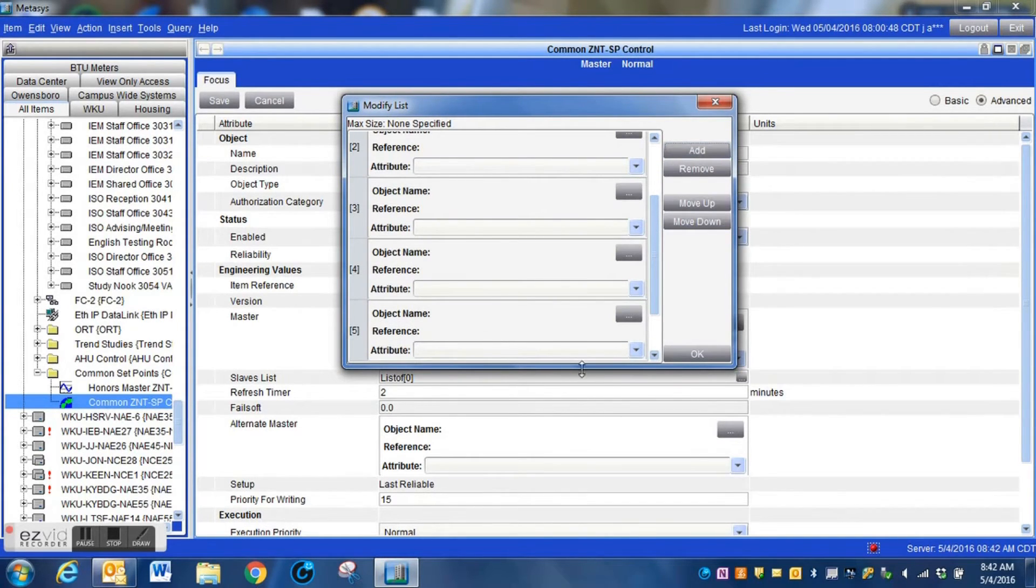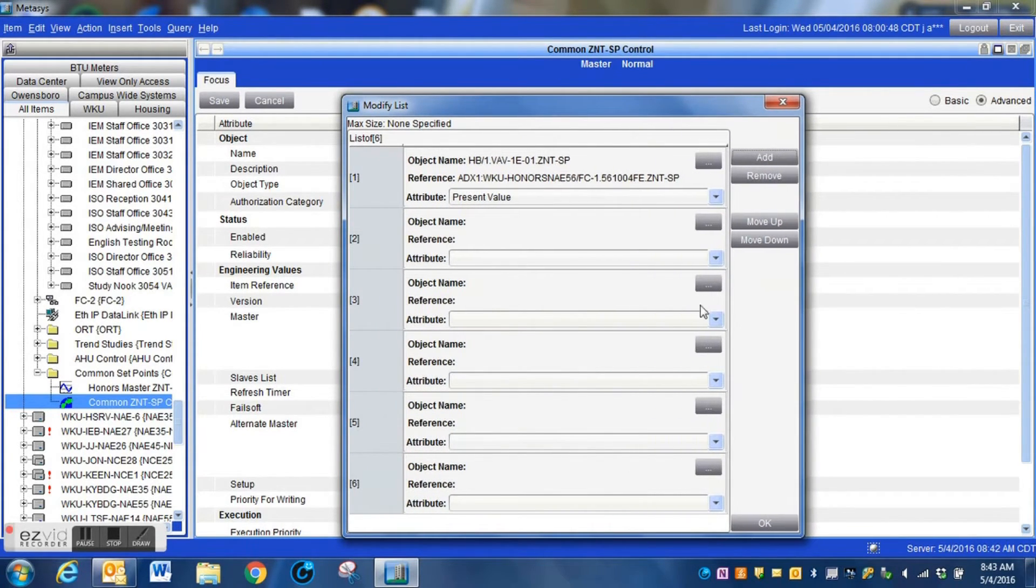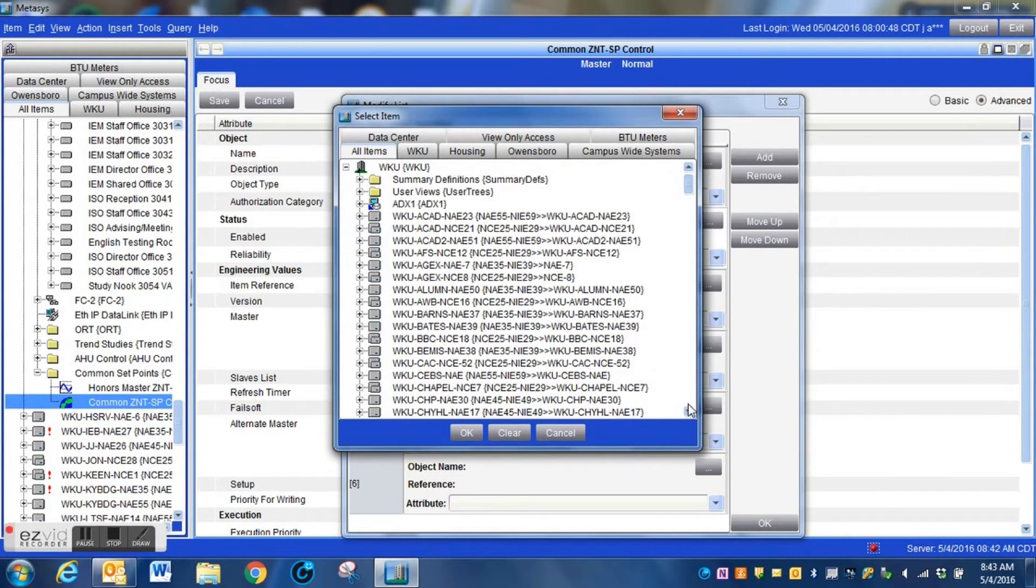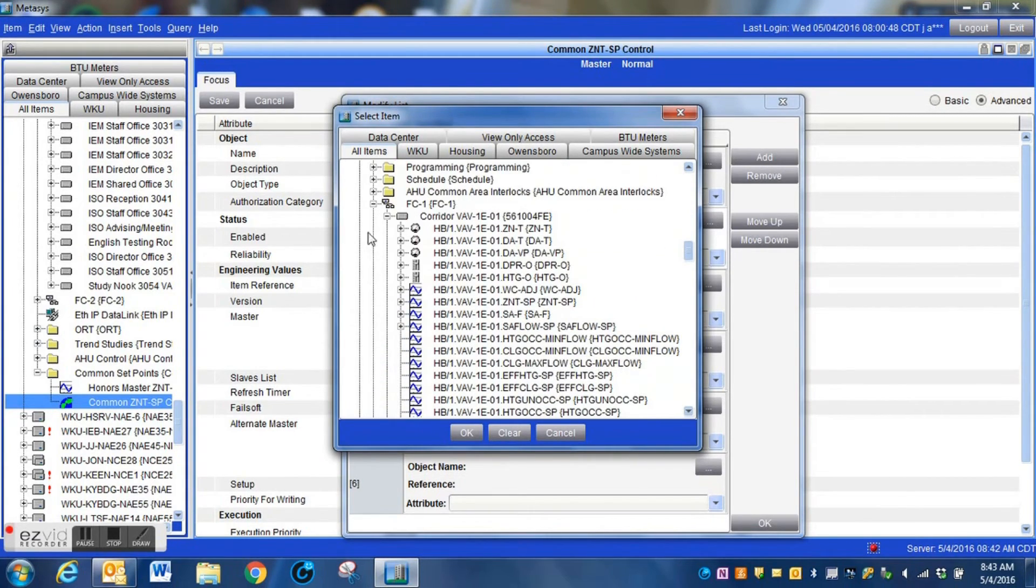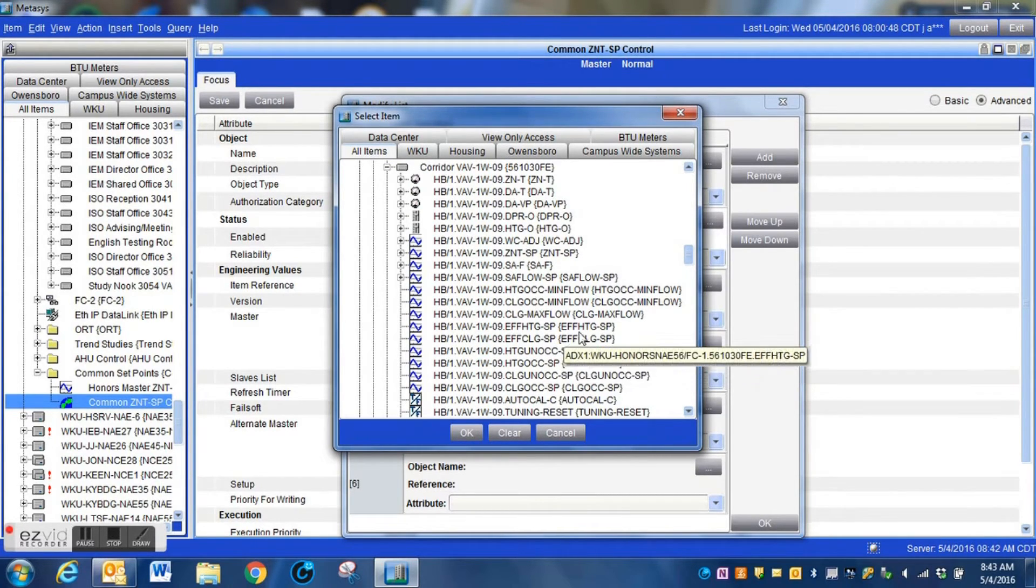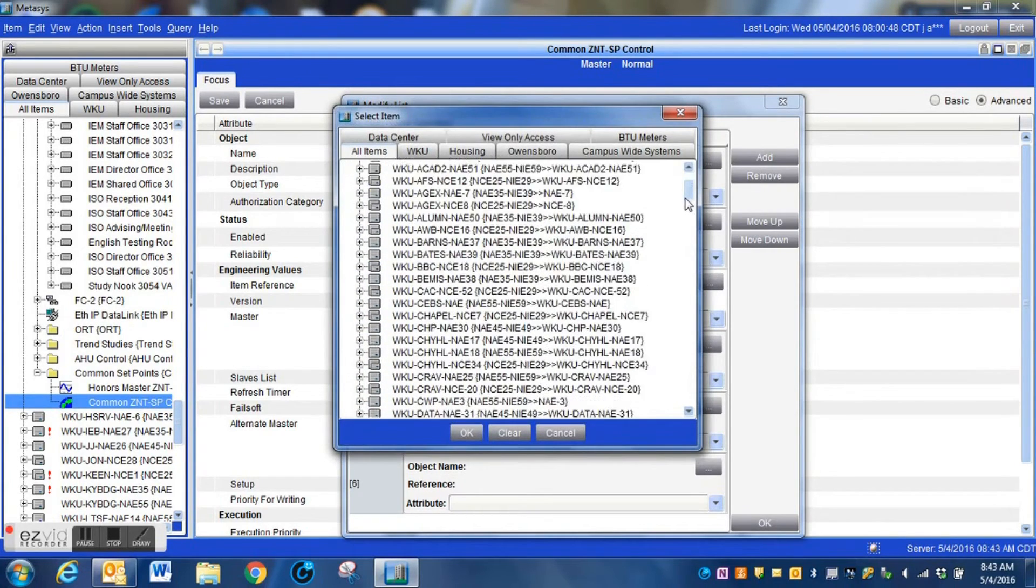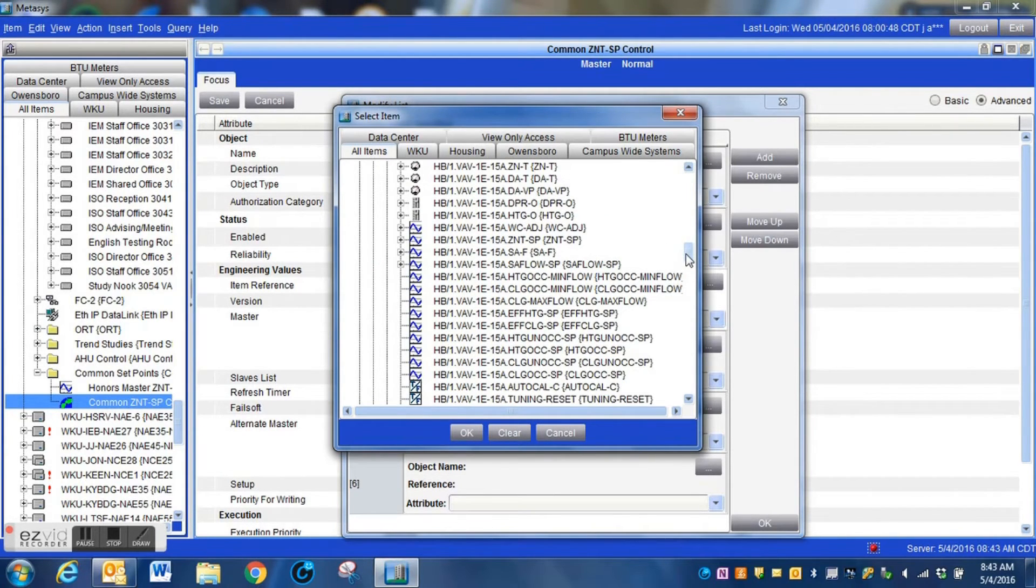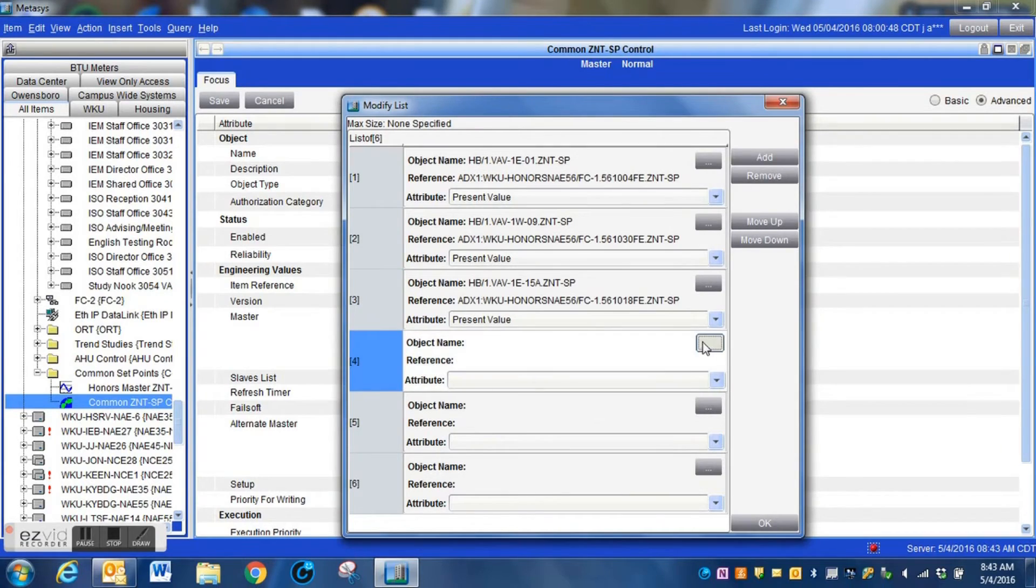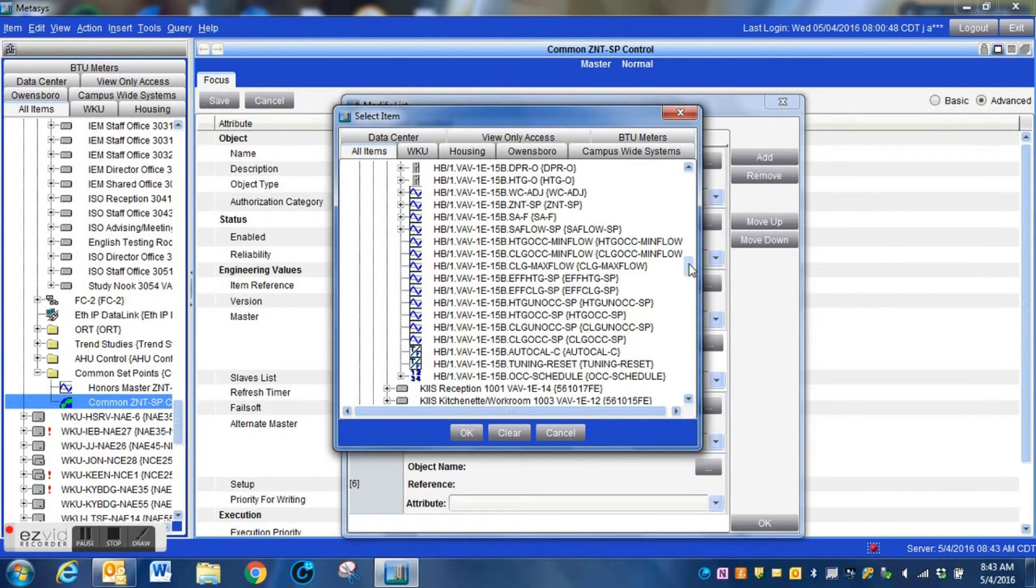We're going to add a few more of these. You can add several, five or six. Add those to your system, go back and find those values within your system, and then save your work regularly. You'll see that it will slow down. The more of these you add to your list, the slower your system is going to perform until you get it completed. Don't worry. It is something that does slow your system down as you're adding these points. But once you get it up and running, you should not notice it. You shouldn't notice the change, any hesitation within your system. These changes, when you do go in and change your set point, it will not be instantaneous to all of the controllers. The logic has to go one device at a time, and it goes right down that slave list, the way that you introduce it.